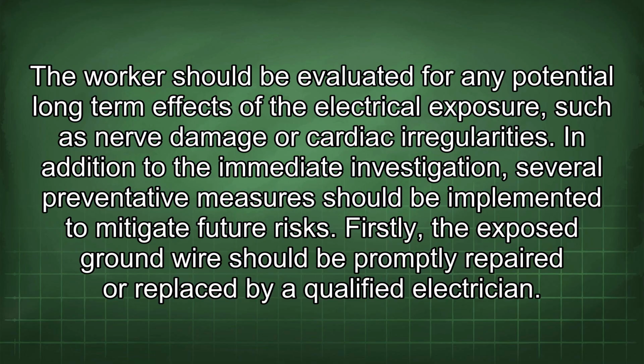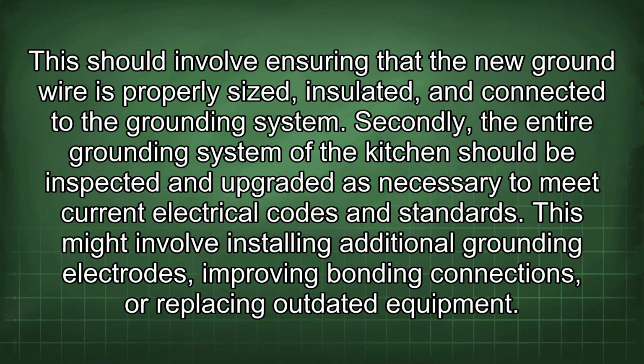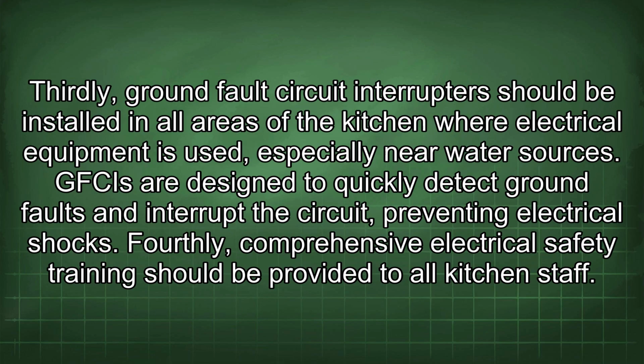Firstly, the exposed ground wire should be promptly repaired or replaced by a qualified electrician. This should involve ensuring that the new ground wire is properly sized, insulated, and connected to the grounding system. Secondly, the entire grounding system of the kitchen should be inspected and upgraded as necessary to meet current electrical codes and standards. This might involve installing additional grounding electrodes, improving bonding connections, or replacing outdated equipment. Thirdly, ground fault circuit interrupters should be installed in all areas of the kitchen where electrical equipment is used, especially near water sources.